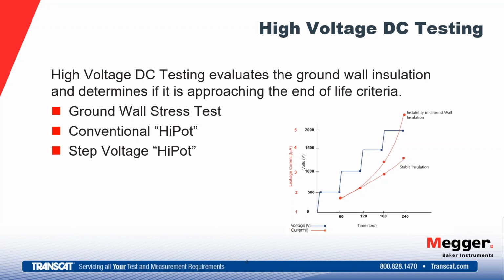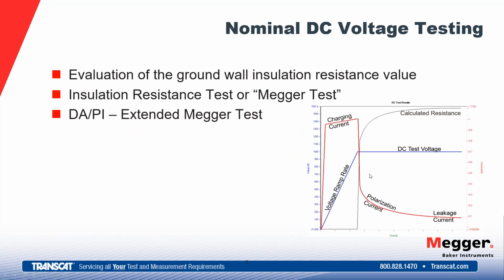We're going to hook up our 3 leads and energize that motor, so all 3 phases will be at the same potential to ground. So any kind of differences there, we're able to see because of the voltage drop. So we're looking at ground wall stresses. There's actually two methods of applying this voltage. It would be the conventional HiPot, which very closely resembles the Megger test. Just as we ramp up to a higher voltage, but then we hold for 1 minute, evaluating the leakage current.